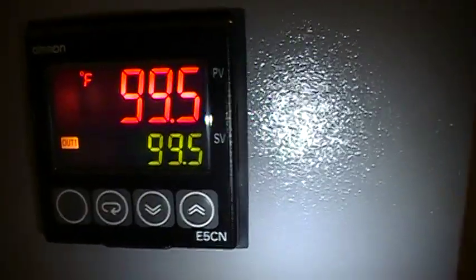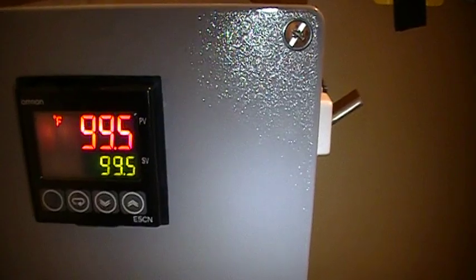The ETC is supplied with 110 volts, and it has a DC output that runs down to the bottom to a solid state relay. As you can see, the relay here is supplied with DC current on this side and AC current on this side going to the element. During the entire time I've been talking to you, you'll notice how constant this thing is able to maintain the temperature of 99.5. It occasionally will go to 99.4, 99.6, but basically throughout a 24-hour cycle you will not have more than a 1/10 of a degree variation in this temperature, so long as you don't open the door or fool with the thermostat setting on it.